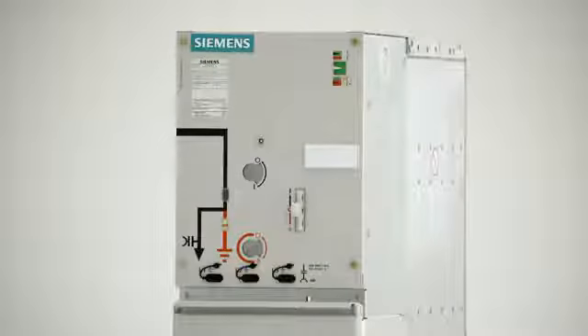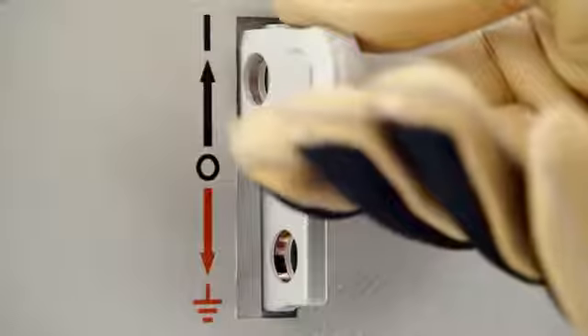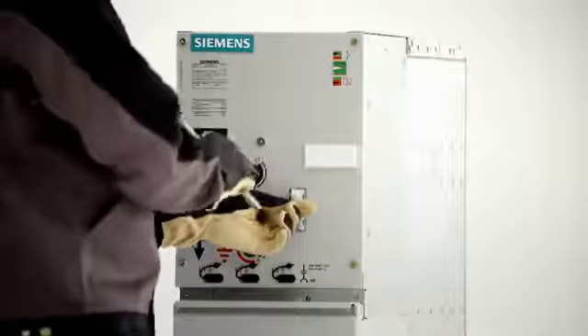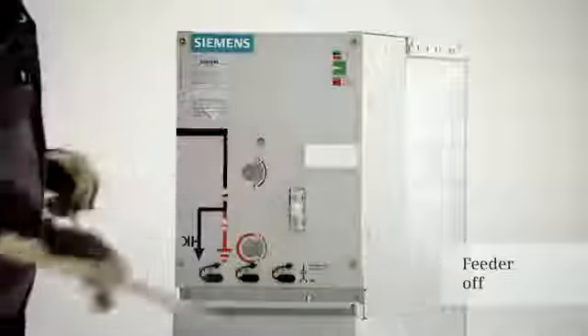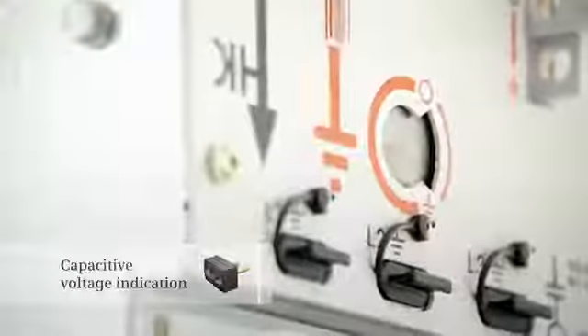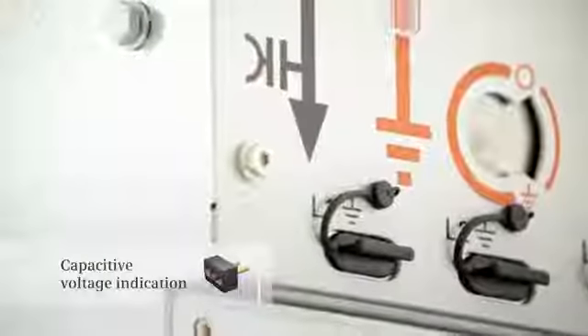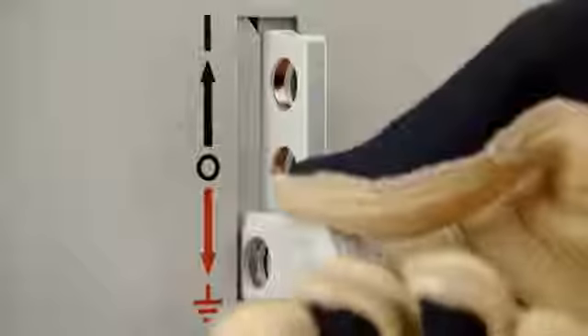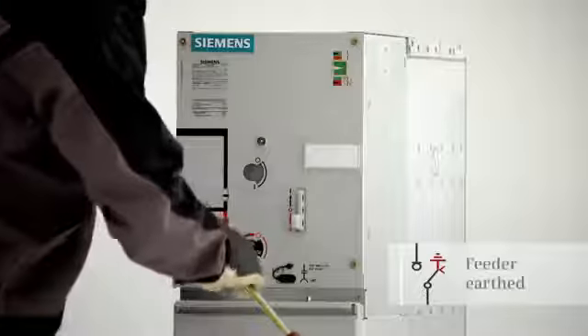When the control gate is pushed up, the actuating opening is unlocked for switching. When the actuating lever is turned counterclockwise until an audible end stop is heard, the 3-position switch switches off the feeder. Safe isolation from supply can easily be checked at the test sockets for the capacitive voltage indicators. To unlock the actuating opening for earthing, the control gate is pushed down. The feeder can then be earthed with the 3-position switch using the operating lever.